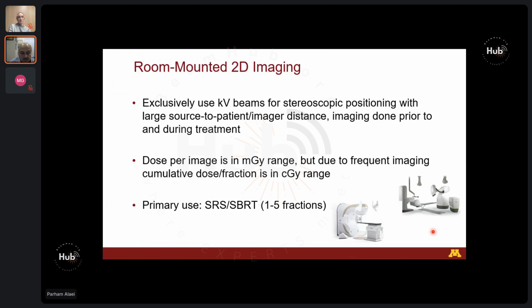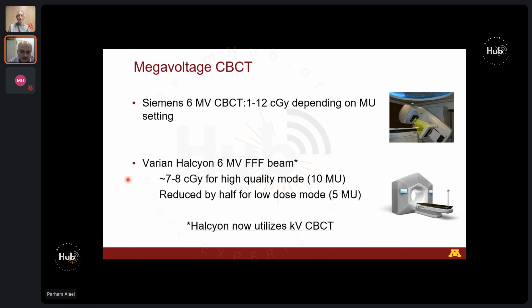And then I mentioned Megavoltage CBCT. Again, they actually have the highest dose if there are any units still out there, especially if the high dose mode is used. And the same thing for Varian Halcyon 6 MV triple F beam. If there is anybody out there using that, it could be pretty high for the high quality mode. Again, this unit now uses a kV CBCT.